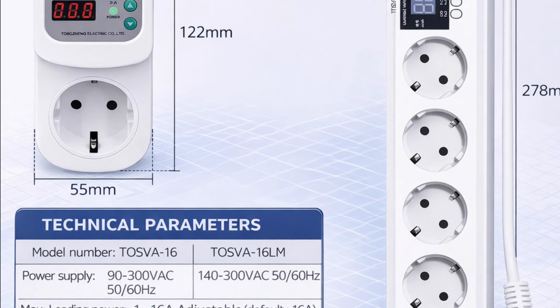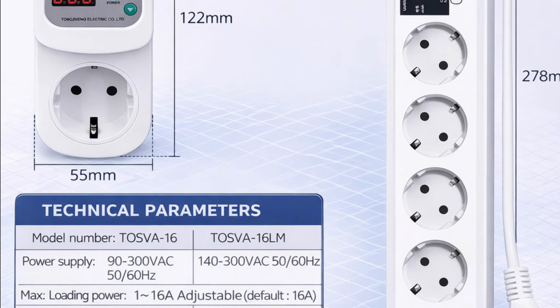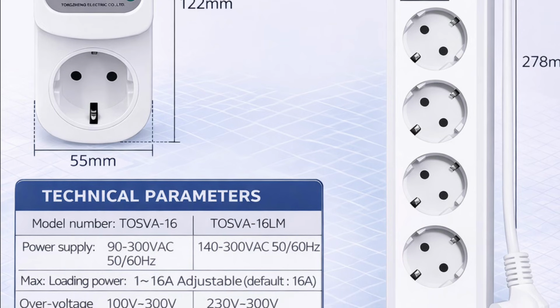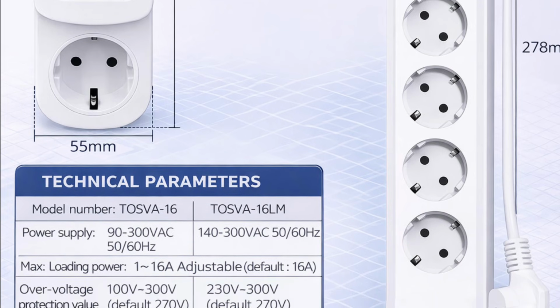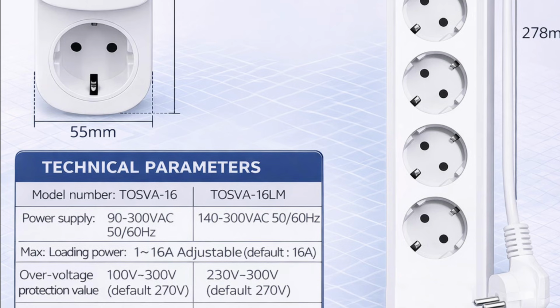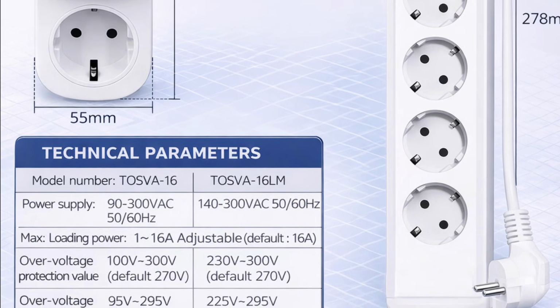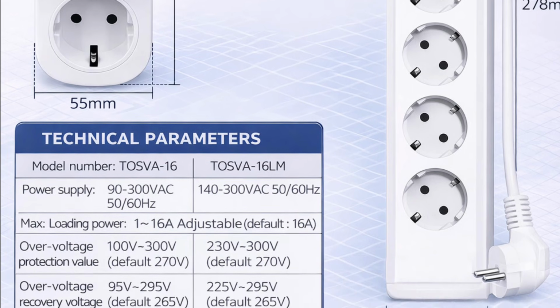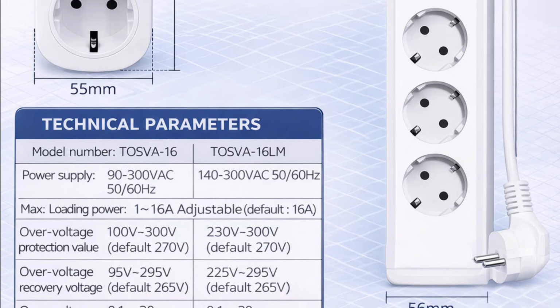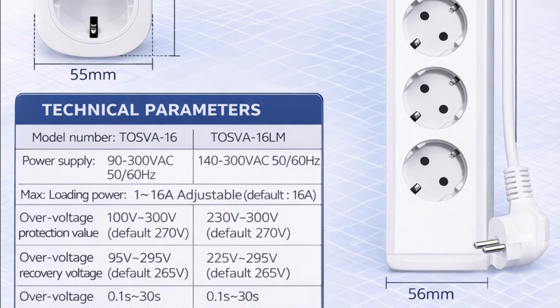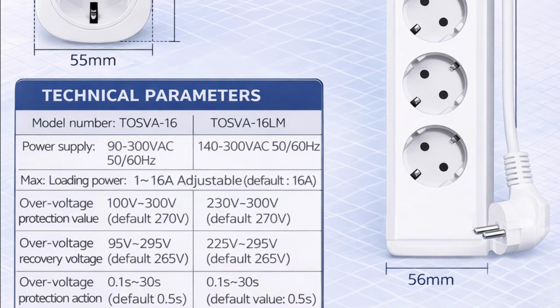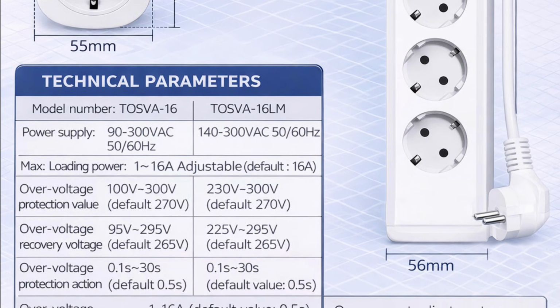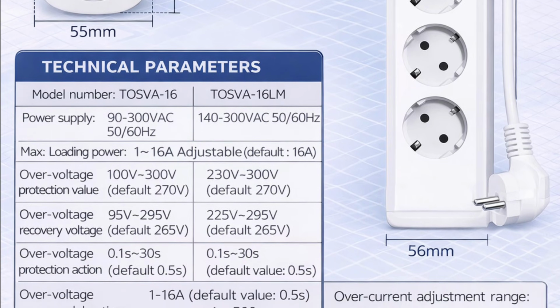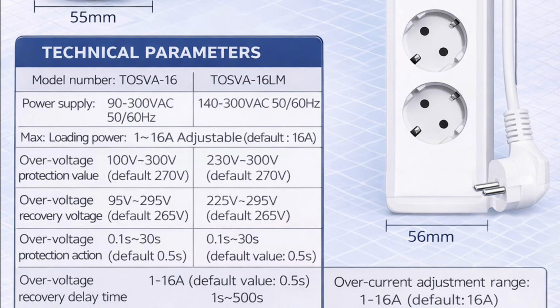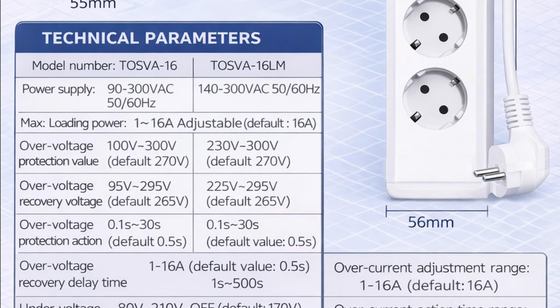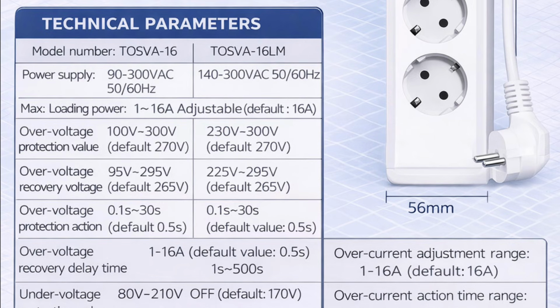The protection response time, the delay of repeated switching on, and the delay when power is applied. All of this can be configured over a wide range for specific network conditions. In fact, these relays can also work as turn-on delay relays, which makes it possible to separate and time the startup of powerful consumers and reduce the load on the network during simultaneous switching on. The power consumption of the relay itself is minimal, less than 2 watts, and the switching life is stated to be around 100,000 cycles. Now to the differences.